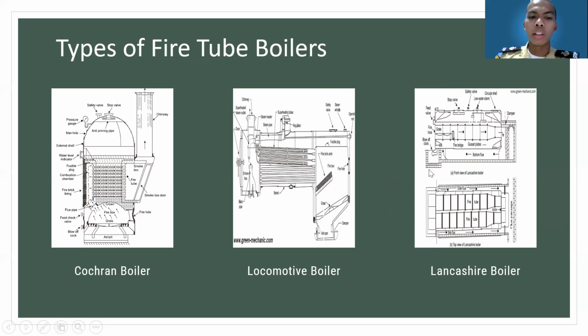So of course, the hot flue gas is produced by heating the fuel, which then hits the water surrounding the fire tubes. So inside the fire tubes, the hot flue gas flows and hits the surrounding water. So the transfer of heat from the gas to the water to make steam takes place at high temperature. So the water and the hot steam are separated where the steam is produced. The steam flows through the anti-priming pipes, and furthermore, the wet steam is superheated, and the dry steam is fed to the steam stop valve. The steam generated is used to operate turbines, which are then used for the generation of electricity.